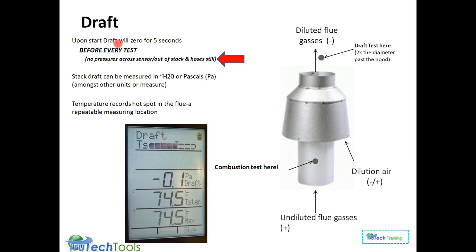When you start up a draft test, there'll be a 5-second period where the draft sensor is zeroing out, and this is true for any of the pressure tests. You have to make sure there's no pressure on the sensor, and the probe is out of the stack, and the hoses are still not moving, because even a small amount of movement in the hose will generate a pressure, and that would cause your zero to be off. And as you can see here, we do have Pascal measurements shown on this screen, and I can show you how you can set that up on your analyzer.